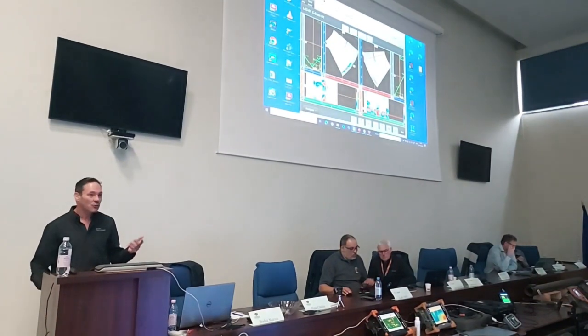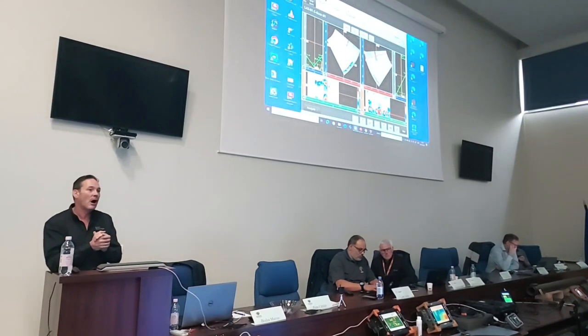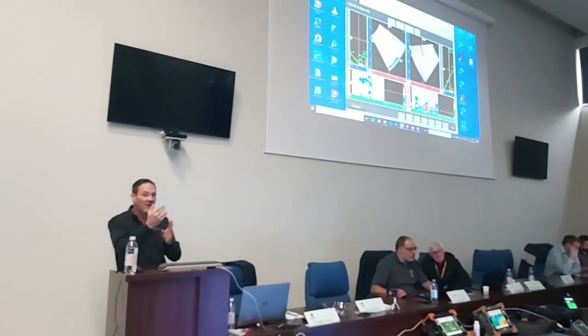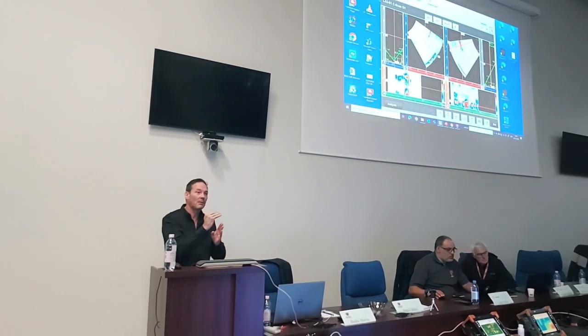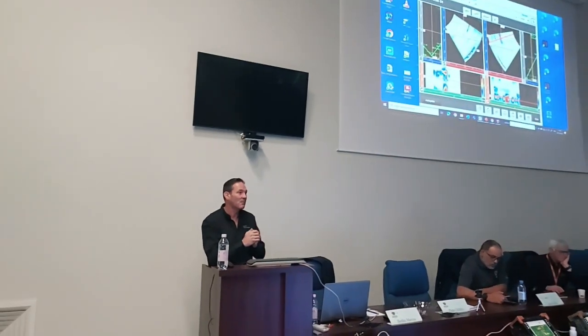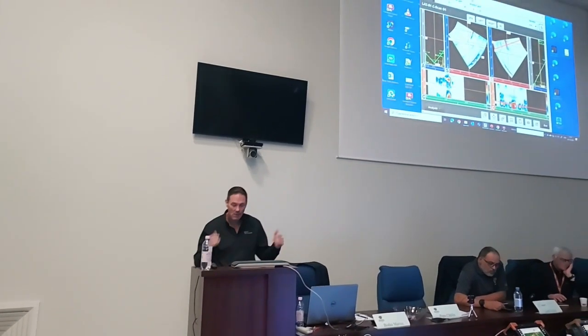With conventional UT, if you find a defect, you're going to have to use the half dB drop method. So you're going to have to use a probe, find the optimum reflection of the defect, move left, so you see half the amplitude drop, and then move right, see half the amplitude drop, and then you have the size of the defect. It's quite imprecise, but it is the way that this type of defect sizing works. TOFD in this case would be a much better solution to do sizing, but we don't have a TOFD setup here.